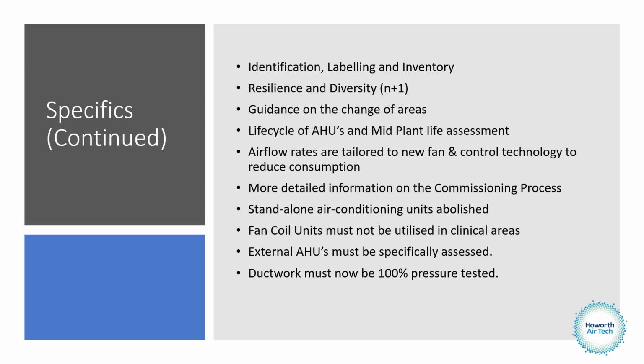So there's AHUs out there on rooftops without heat tracing on, glass traps. There is louvers that are incorrectly positioned, drawing water through the intake. This is out there. I've seen it with my own eyes. We need to stop this happening. And then finally, ductwork must be pressure tested. Medium pressure ductwork, class B, 3%, and that's noted in DW144, so that's a BESA document.